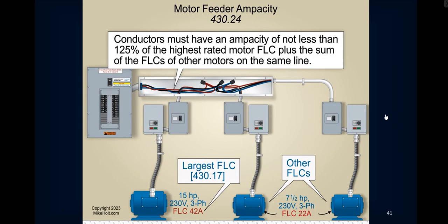They didn't do the calculation for me, so I'll just tell you. We're going to take that 42 amps, multiply it by 125%, and whatever that ends up being, we'll take that and add the ampacity of the other two motors. So I would take 42 amps times 125%. That's 52.5 plus 22 amps plus another 22, because there's two of them with 22 amps. That's 96.5. So at that point, I can say, okay, I've got a load of 96.5 amps. Now I can go to table 310.16 and size my conductors. Now I'm ready to install.